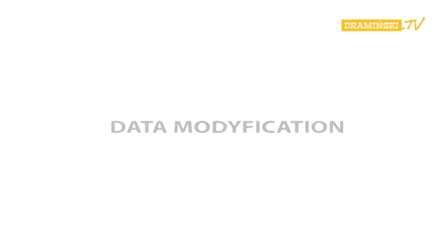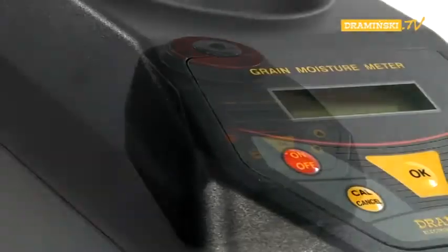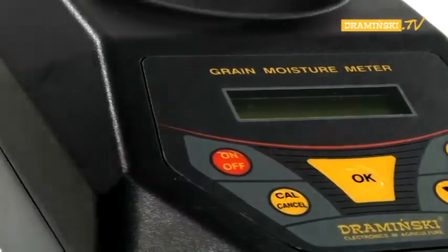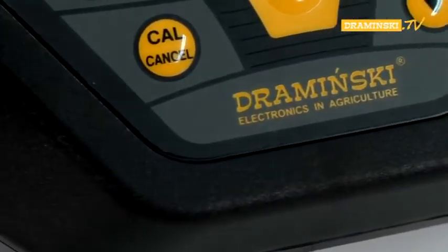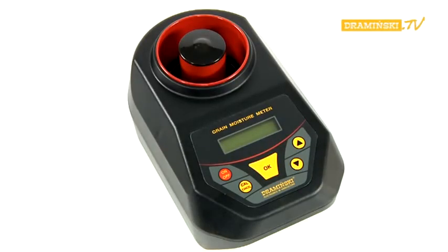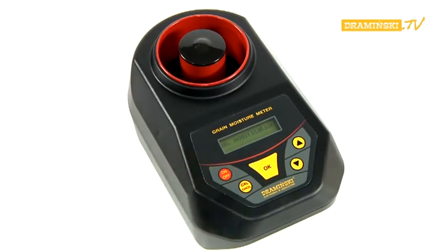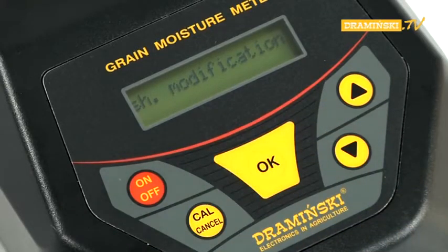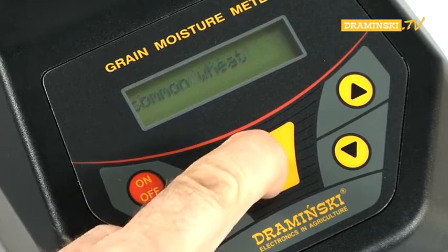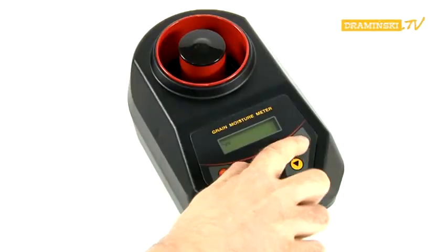The Dramiński Grain Moisture Meter has a function that allows the user to modify data — in other words, to calibrate the device by correcting the coded humidity curves for each species of grain. To carry out the required corrections, turn the power ON with the ON-OFF button while the CAL button is pressed. Use the arrow button to choose the modifying data function and confirm it by pressing OK. The name of the last measured sample appears on the screen, which can be changed using the arrow keys.